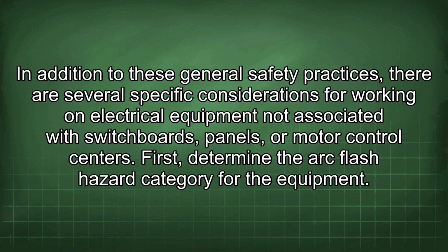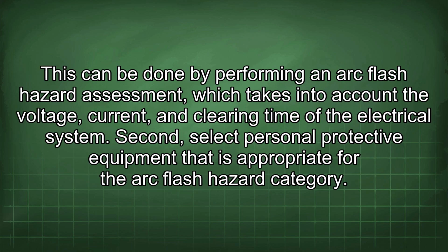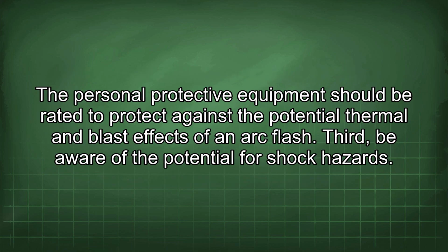In addition to these general safety practices, there are several specific considerations for working on electrical equipment not associated with switchboards, panels, or motor control centers. First, determine the arc flash hazard category for the equipment. This can be done by performing an arc flash hazard assessment, which takes into account the voltage, current, and clearing time of the electrical system. Second, select personal protective equipment that is appropriate for the arc flash hazard category. The personal protective equipment should be rated to protect against the potential thermal and blast effects of an arc flash.